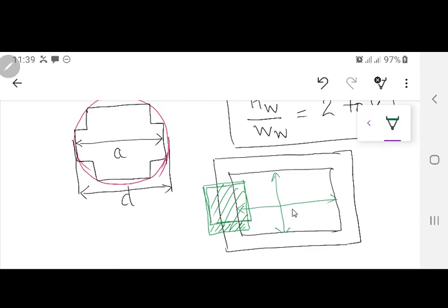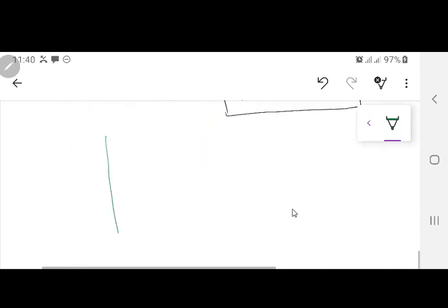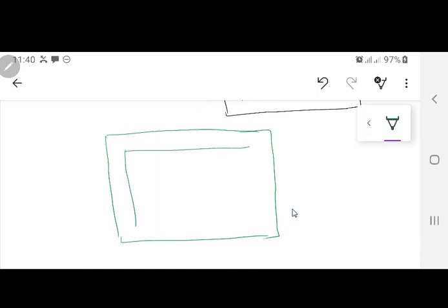But when you are designing big transformers, supposedly something 100 kVA, 200 kVA or 400 kVA, just like this outside our department, then in that case you are not going to go towards the tank design first. You are going to design the limb, LT winding design first, oil duct, and then based on the width of your winding, supposedly, what I mean by that, if you are going the other way, this is the core, on top of this you have designed the LT winding.